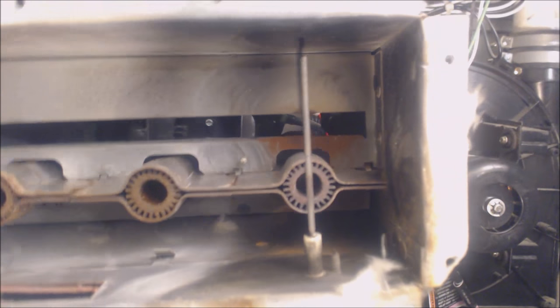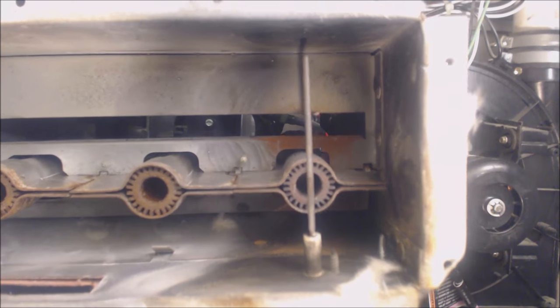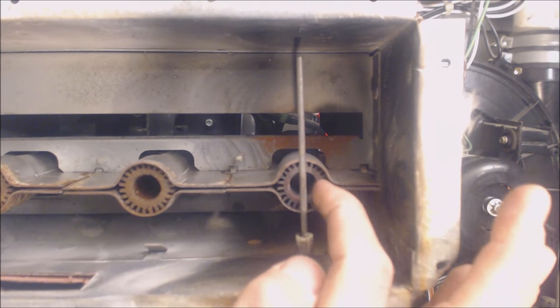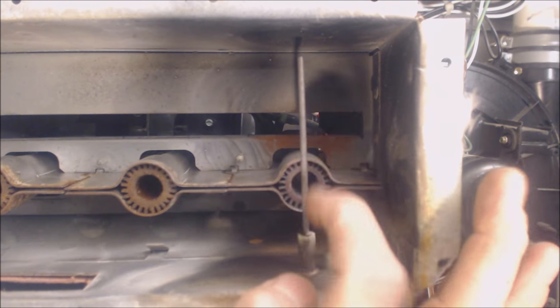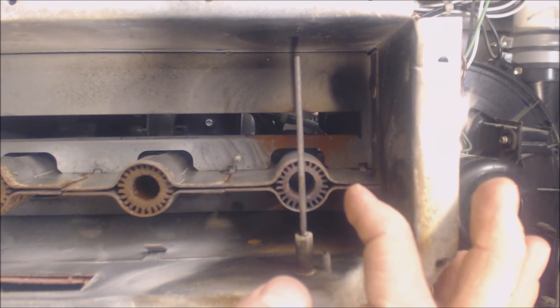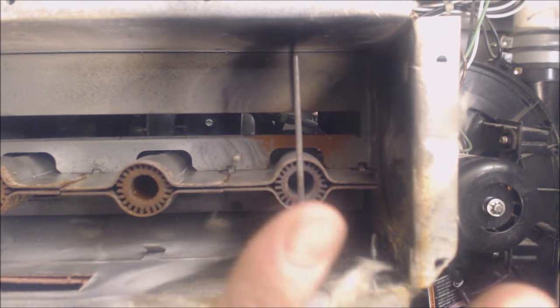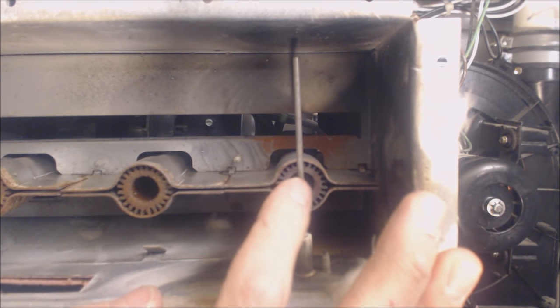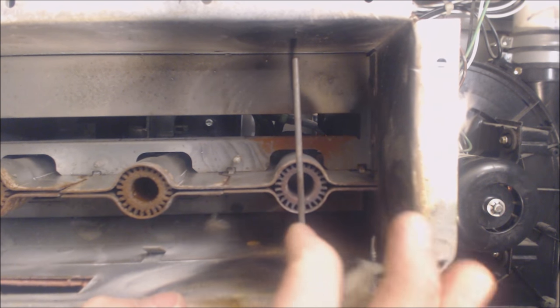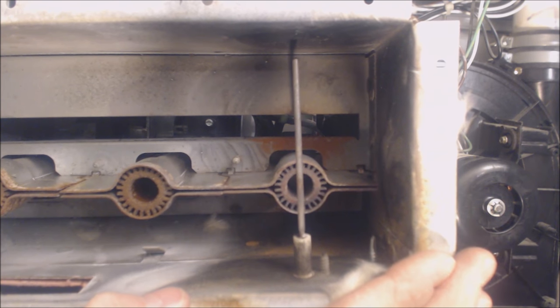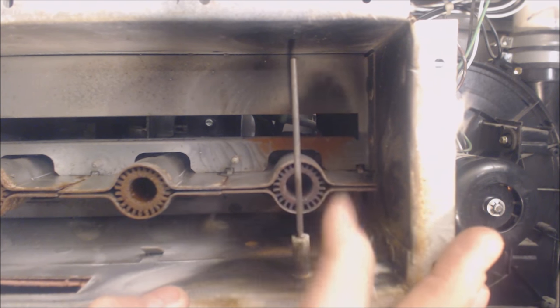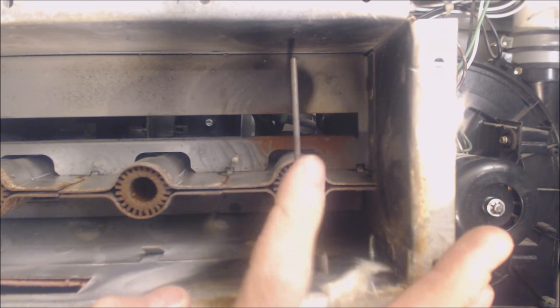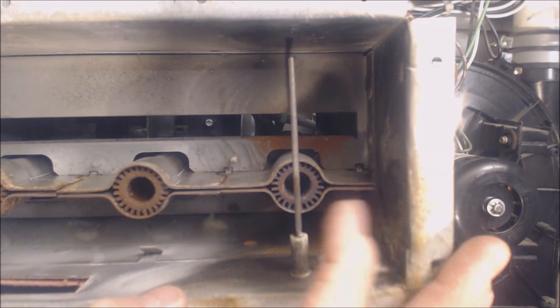So right here is the burner retention head right here and here's the flame rod. So as the flame shoots this way, it goes through the flame rod. The flame rod is just a stainless steel rod and if oxidation builds up on it, you're not going to have the voltage going into the flame properly.